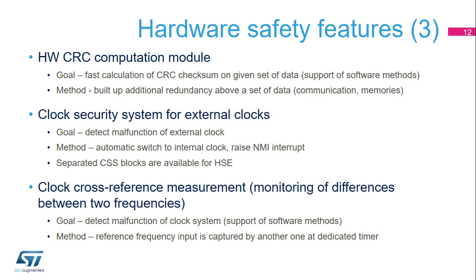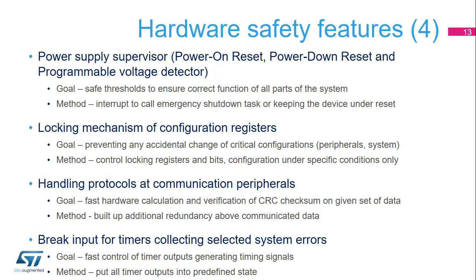This slide lists additional safety features dedicated to cyclic redundancy check, or CRC computation, and clock control. Nevertheless, all the tests listed here, with the exception of ECC, are exclusively dedicated to the detection of failures. This is why additional software tests must be added when compensation or an additional check is required — for example, to achieve a higher level of SIL. In this case, the user must ensure that the software testing period takes into account the process safety time.